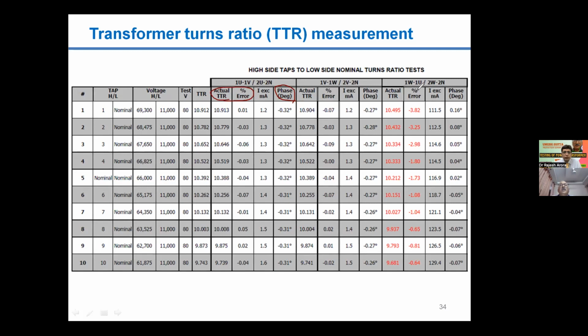Earlier, when these kits were not available, we were simply doing the voltage ratio test. At that time we were not knowing about the phase angle error by doing a simple voltage ratio test. But nowadays, by doing this test through test kits, even the phase angle errors can be measured. Next.